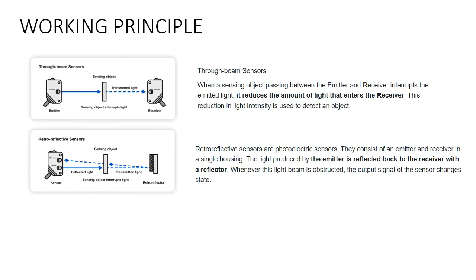The second type is the retro reflective sensor. Here we have a sensor and a retro reflector. The emitter and receiver are in the same module — unlike the through beam type where they are separate. We also have a separate reflector piece. When there is no part in between, the light is transmitted and the reflector reflects it back, which is then received by the receiver in the sensor.